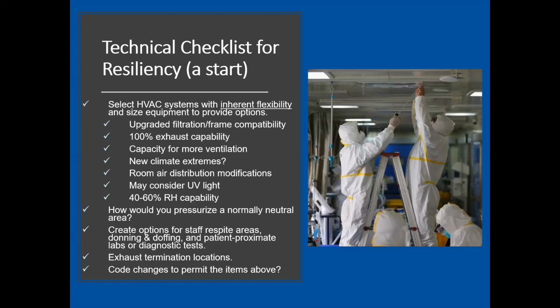And so ASHRAE is looking at code changes to permit some of the items above. We need to think about energy codes and say, how can we allow some of this inherent flexibility and capacity to be designed into systems, without the restrictions that the energy code sometimes puts on us, saying you can't design a coil with this much capacity because it's not necessary. Well, maybe not necessary in ordinary times, but I think we'd all agree these are not ordinary times.